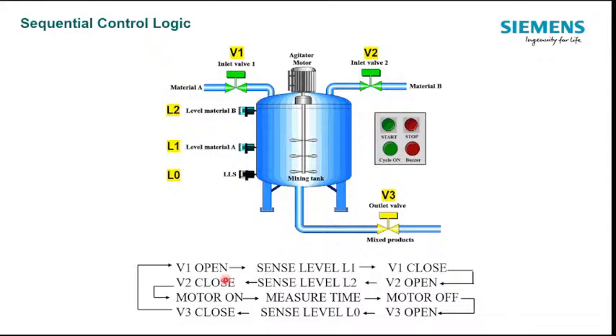So in the process, once I press the start push button, first V1 will open and material A will be getting filled. Once it reaches L1, level L1 will be sensed, V1 will be closed and V2 will open. Then material B will be getting filled, and once it reaches level L2, it will sense level L2. Then V2 closes and the motor turns on.